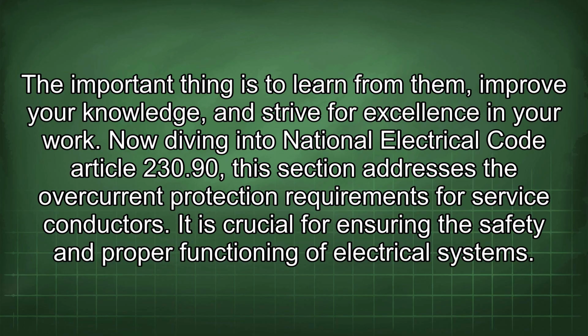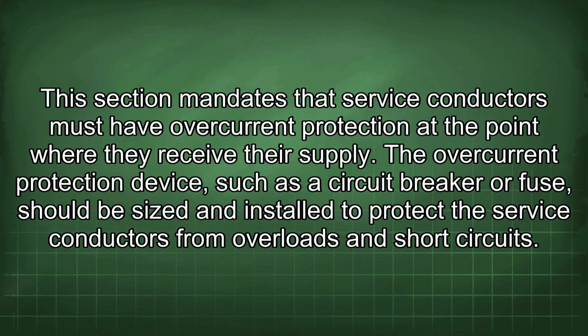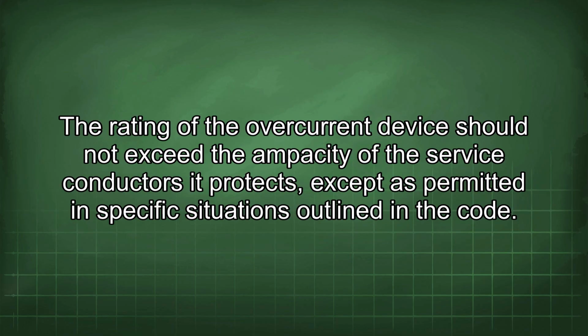Now diving into National Electrical Code Article 230.90, this section addresses the overcurrent protection requirements for service conductors. It is crucial for ensuring the safety and proper functioning of electrical systems. This section mandates that service conductors must have overcurrent protection at the point where they receive their supply. The overcurrent protection device, such as a circuit breaker or fuse, should be sized and installed to protect the service conductors from overloads and short circuits. The rating of the overcurrent device should not exceed the ampacity of the service conductors it protects, except as permitted in specific situations outlined in the code.